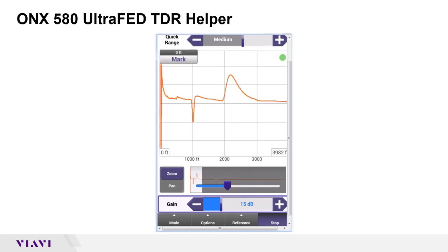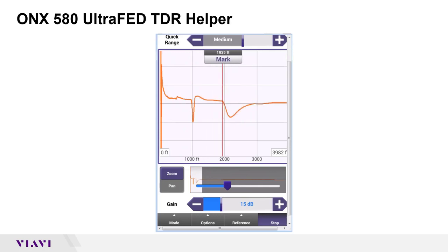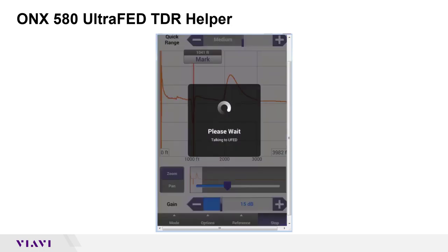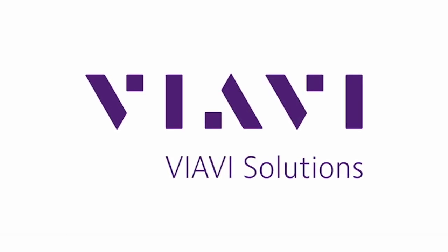The counter in the top right is counting down. You can see a short go on, then it goes open. Running the cursor from left to right, I can see that my short and open is happening at about 1,935 feet — so I know this particular short is definitely well bracketed. Once the timer times out, it turns the UltraFed off and into its through state. Pretty simple procedure, but very helpful when you want to know for sure that you've got your fault bracketed and can see out to where you've connected the far end device. I hope this video was helpful — thanks very much.